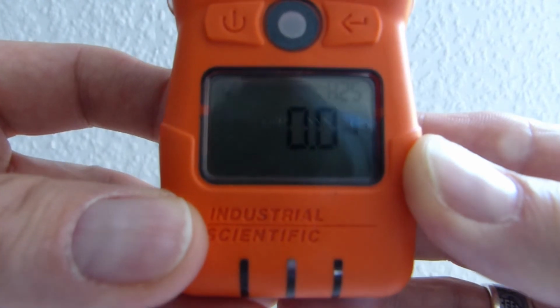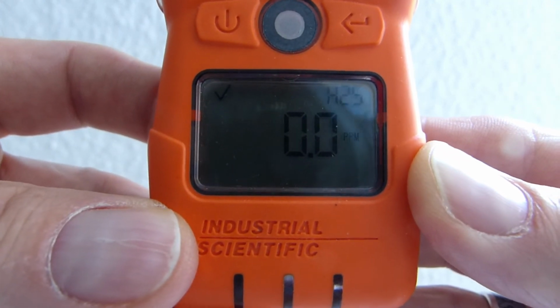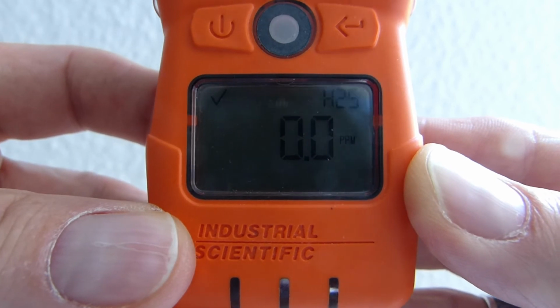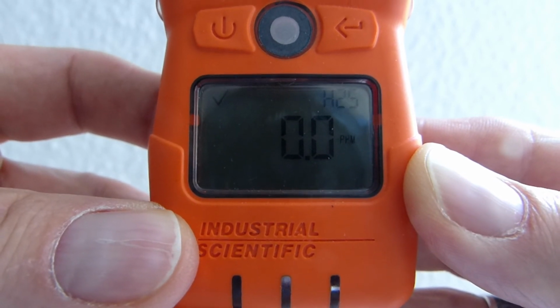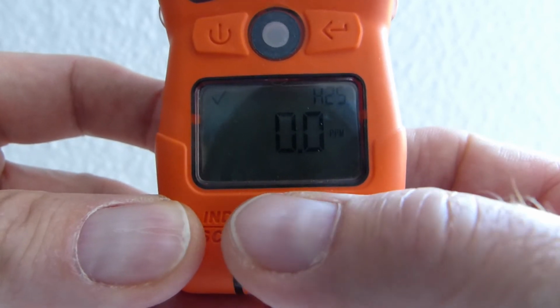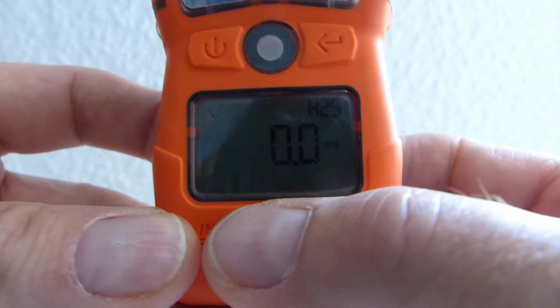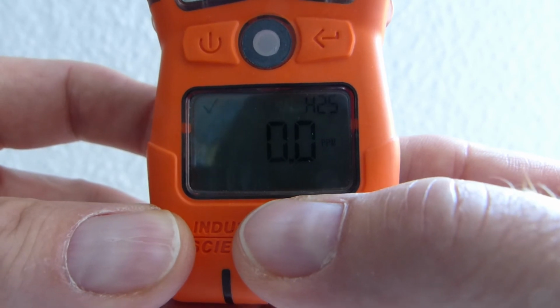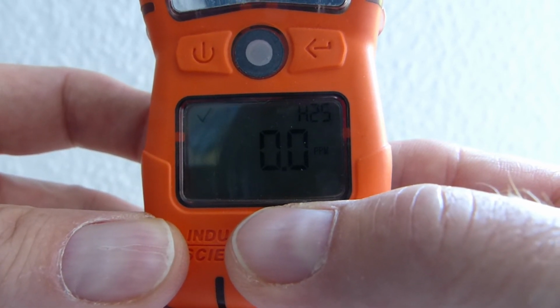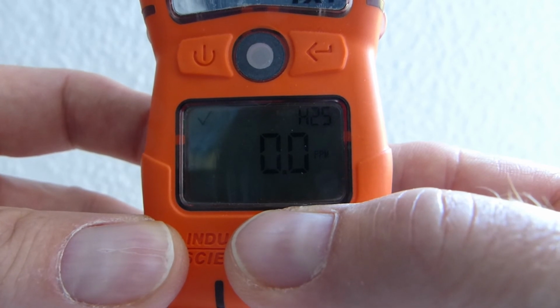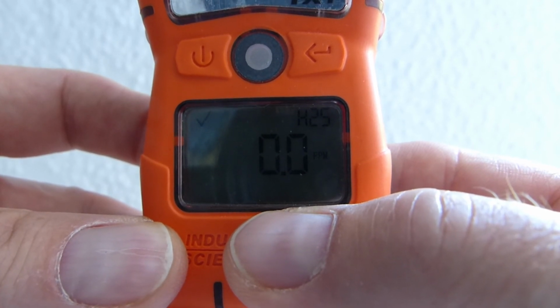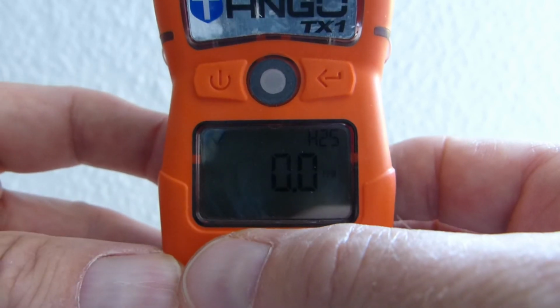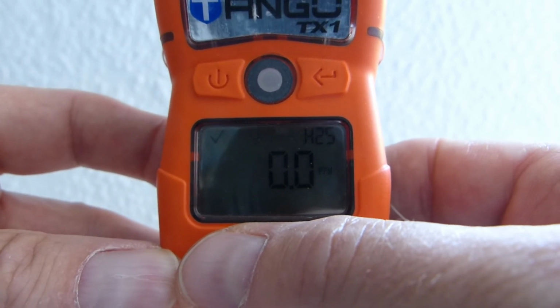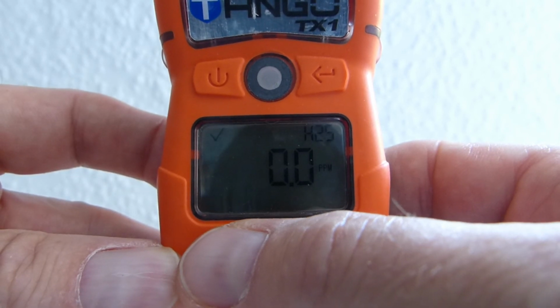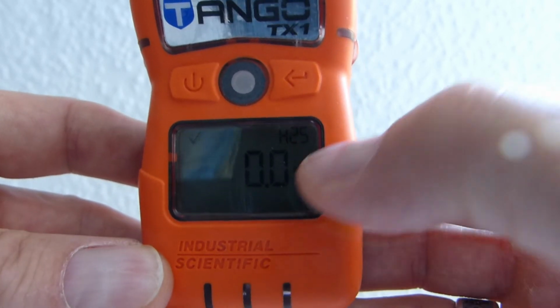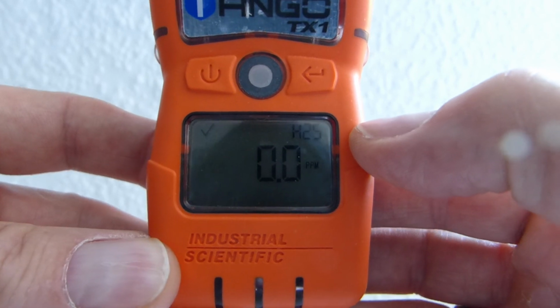On the display, you typically would just see the readings, the check mark and the H2S indication as well as the ppm. On the lower part of the display, if the calibration is overdue, it's going to be indicated here with a check mark and an exclamation mark and a schedule information and a cylinder with a C in it for calibrations. If there is an SE with a number, please give the instrument for service, as there is something wrong with the sensors. If there's any other error message on the screen, please give it to service as well.